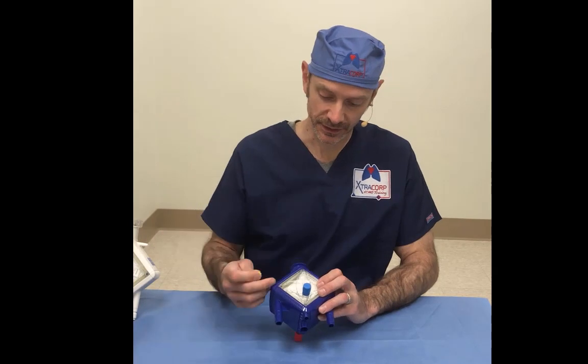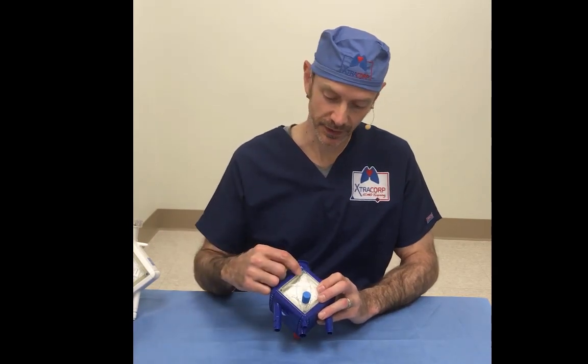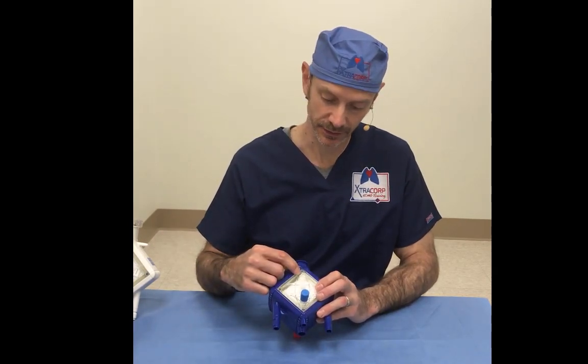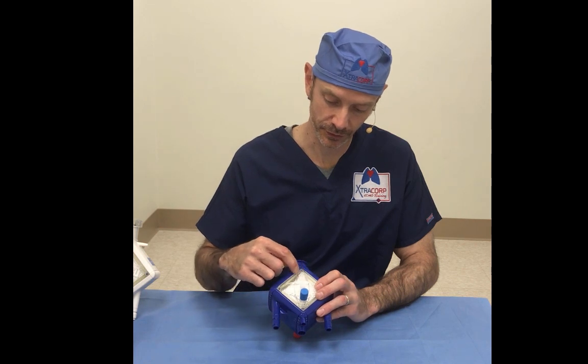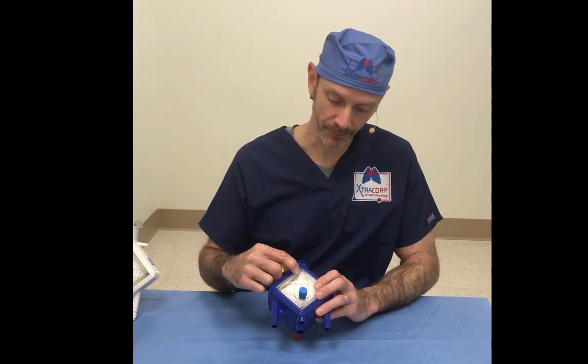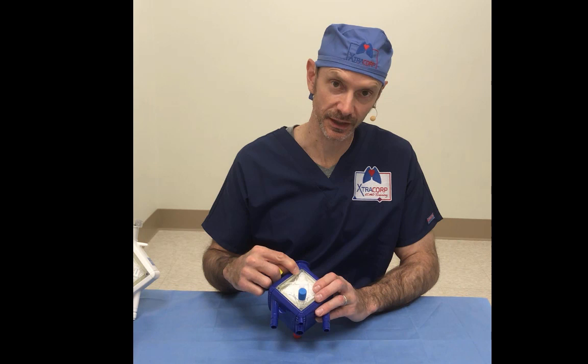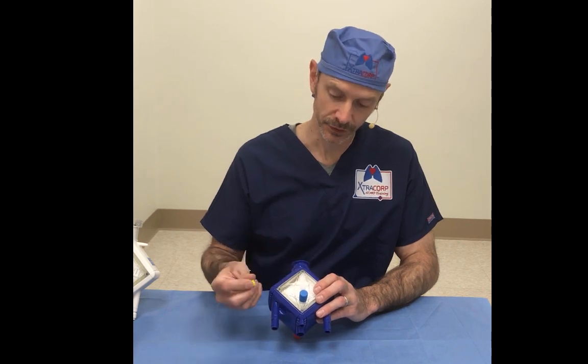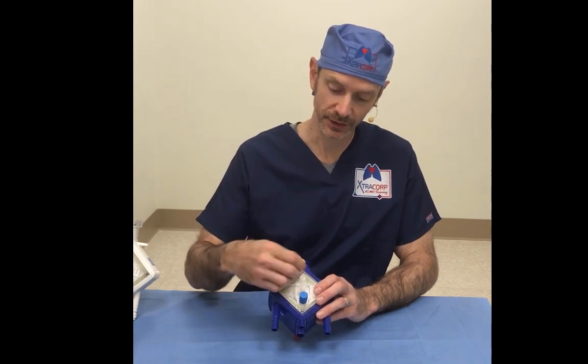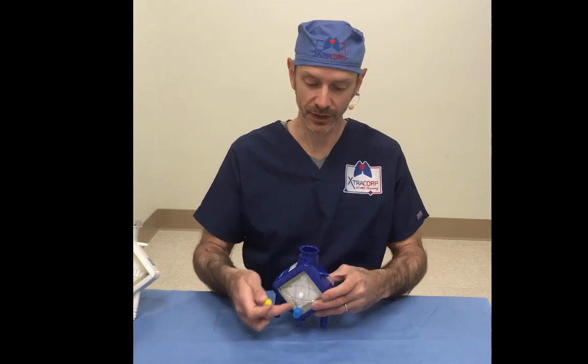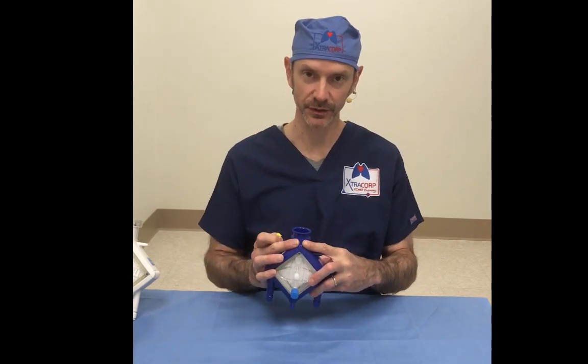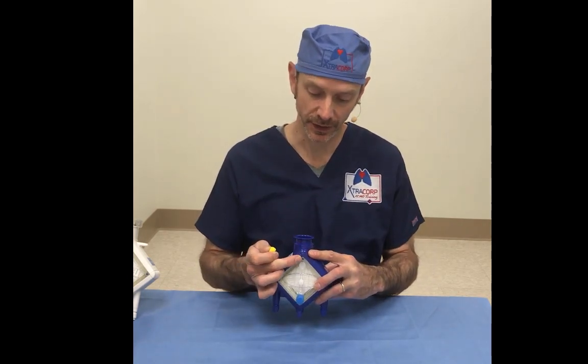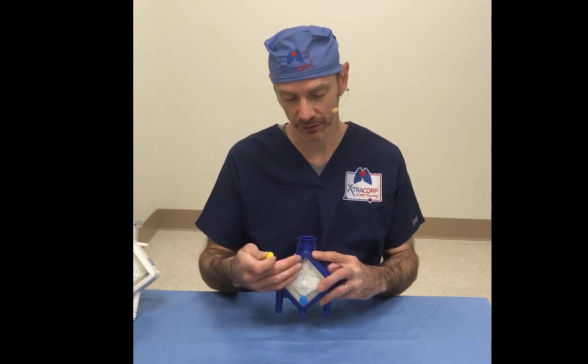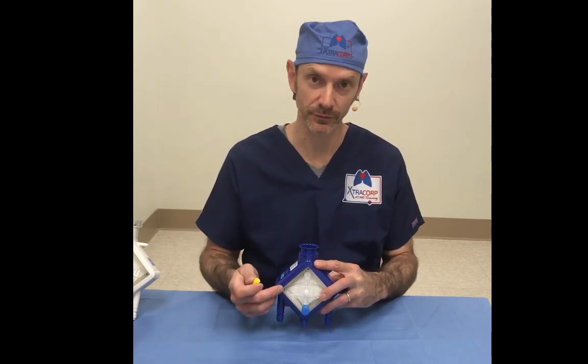The one at the top in all 3 units is a gas vent. The close-up here will show you that there's a membrane back there that lets air out but does not let fluid across. So if there's air inside this device, you take off the yellow cap. Air is channeled to the top based on the geometry of the oxygenator, and the air wicks across. Once the air is gone, the fluid touches the filter and nothing moves then.